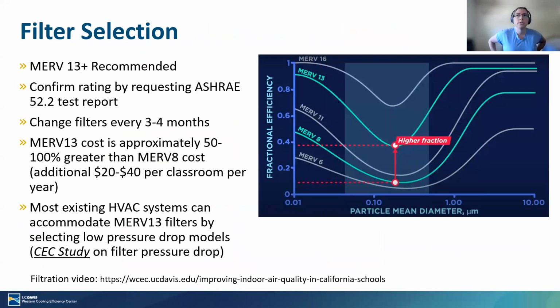Okay, I'm going to switch gears to filters. So I mentioned that MERV 13 is recommended. I just want to talk a little bit about that. So here's a plot of mean particle diameter with filtration efficiency. And so you can see that it's actually these particles that are in the middle, in the range of 0.1 to 0.3 microns. These are the hardest to filter.